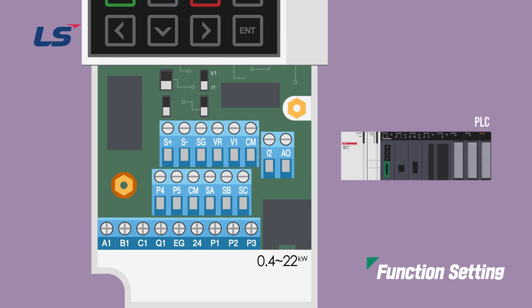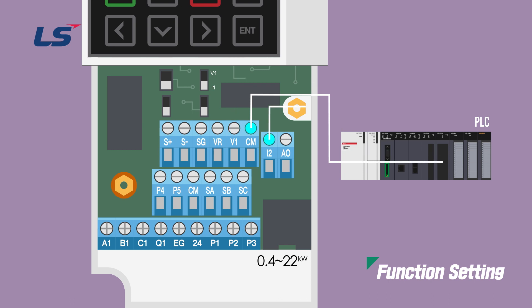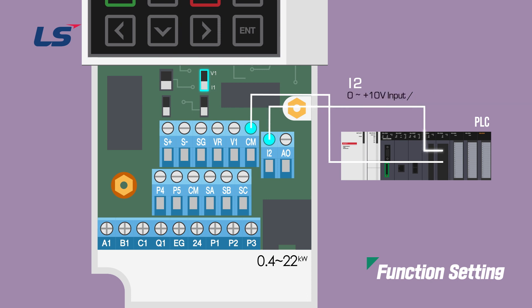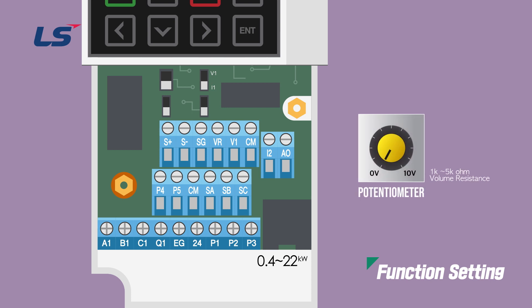When inputting the output voltage of an external device, wire using the V1 and CM terminals, or I2 and CM terminals. The I2 terminal becomes a voltage input terminal that receives 0 to 10 volts when the analog voltage current input terminal setting switch is placed upward, and when it is placed downward, it becomes a current input terminal that receives 4 to 20 mA. When using the AC drive's internal power, wire a 1k to 5k ohm volume resistor to VR, V1, and CM.